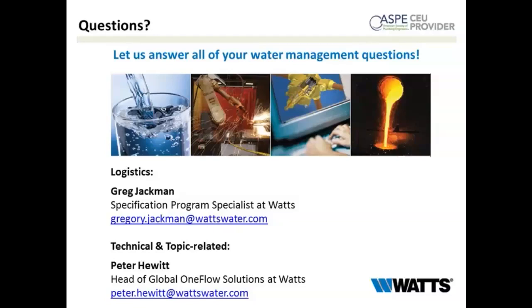All right, and this refers back to a previous question as well. To expand on the replacement based on pressure drop question, can you determine if the media needs to be replaced before the 2 or 3 year time by looking at pressure drop across the TAC system? No. Pressure drop, as I said, is not going to be impacted through the system other than a less than 15 PSI drop, and that won't affect necessarily the media. And then afterwards, in getting water distributed up through commercial buildings with booster pumps and the like, you can control increases to pressure.